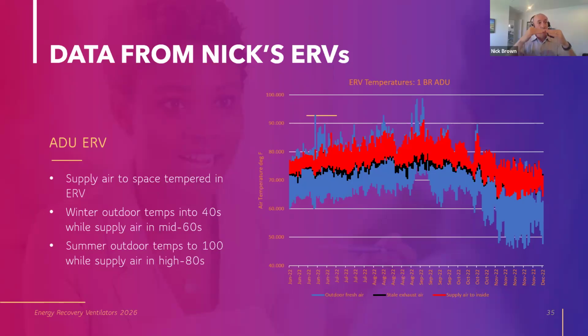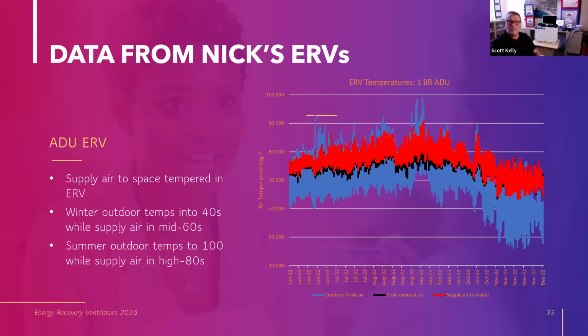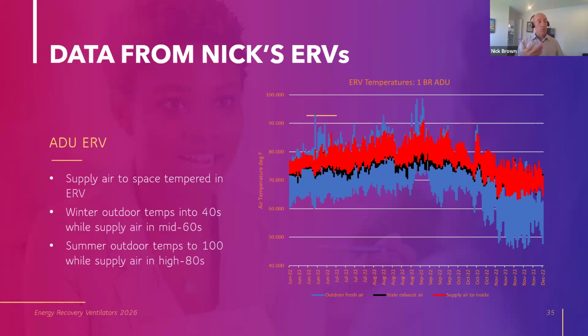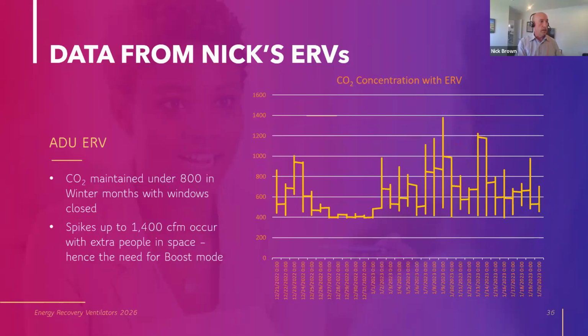But overall, it's slightly elevated above the average of the blue bars because of the heat of the fan. And that's something for you to consider. And that's part of, I think, why ERVs aren't that popular in Palm Springs, where it's extremely hot, because that fan energy adds to your cooling load, right? And so these tend to perform better in my modeling in heating dominated climate zones, 1 through 5, 16, 10 and 12. But you'll also find benefit, especially from efficient ERVs, all along the coast as well. So I thought that illustrated it nicely.